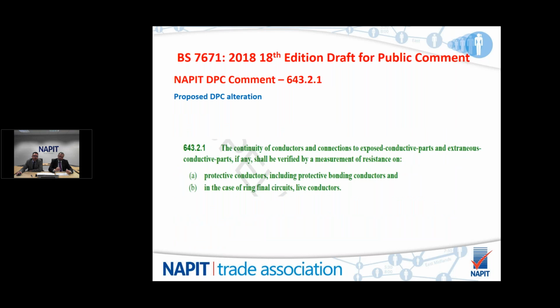The next one we're going to look at is regulation 643.2.1. And as we discussed in our last webinar, the Part 6 regulations have changed numbers. The majority of them stay as they are, but this one does change, as you can see from the wording of it. It states that continuity of conductors and connections to exposed conductive parts and extraneous conductive parts, if any, shall be verified by measurement of resistance on protective conductors, including protective bonding conductors, and in the case of ring final circuits, the live conductors as well as the protective conductors. So it's a change to a verification by measurement of resistance for protective conductors.